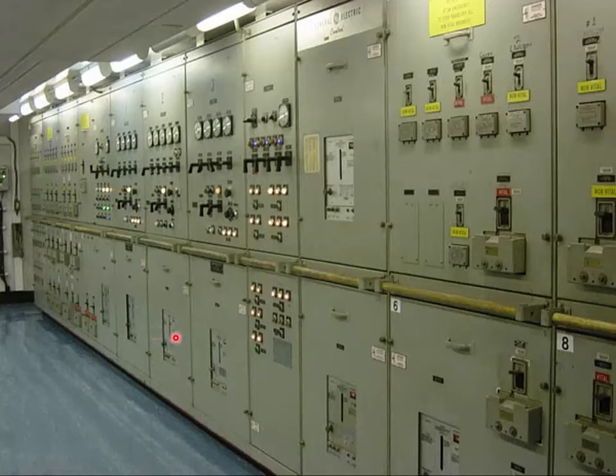These are their motorized circuit breakers that would open in case of an overload. Then I believe this upper one here is going to be your tiebreaker in the engine room on the Bear itself. And these are motorized breakers. Now, these other circuit breakers are manually actuated, and you should already know that you close them by lifting up on the handle until it latches up.